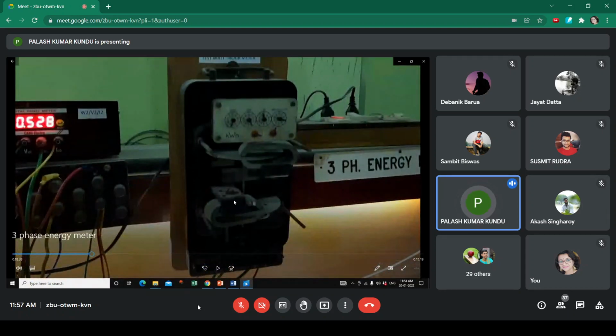Now you can see that the brake magnet and the induction disc are on an open system, the front chassis has been opened up. So this is a registering mechanism decade dial. So this part is for the induction disc type, which moves in the brake magnet. Without the brake magnet, there is no steady speed. And the two discs are coupled to the mechanical linkage. And this registering mechanism on the top uses a set of pinion arrangement. So please note or see the construction and details of the energy meter practically.